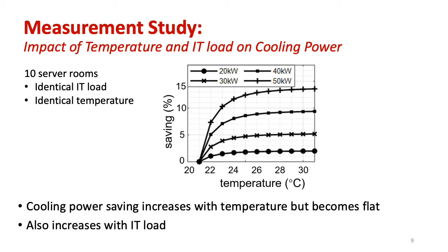The figure shows the relative cooling power saving versus the temperature set point under different IT loads. We can see that the saving increases with the temperature, but it becomes flat. This means that it is worthwhile to increase the temperature set points from the current very low levels.